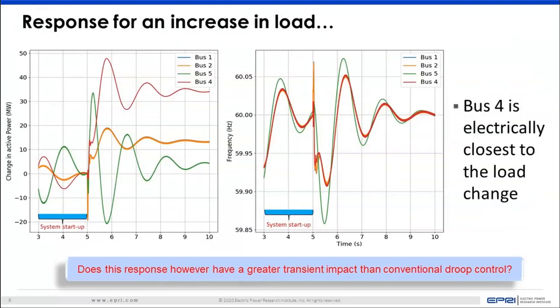Now, for an increase in load, this is what we found out. What you see on the left-hand side is change in active power across the variety of resources, and what you see on the right-hand side is frequency in the entire system. Now, this entire setup was run in EMT, which takes quite a bit of time, so once we got this small amount of system startup simulation where we know it is going to settle down, we just applied the disturbance. So even though we would have ideally liked a flat start in the first few seconds, just for ease of discussion, we have not gone to that extent.